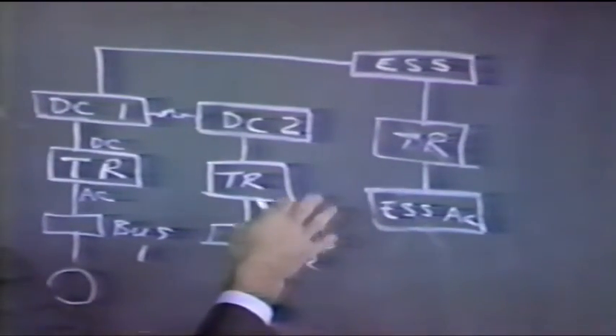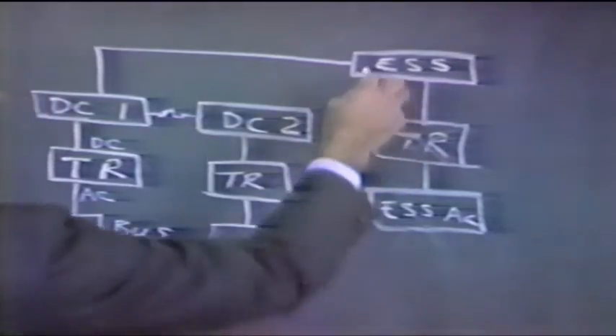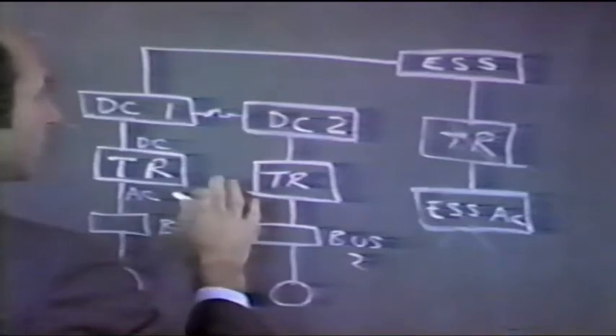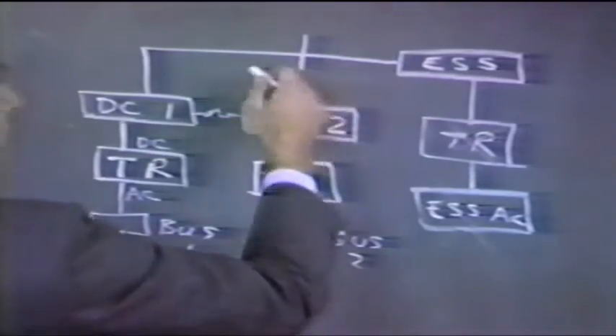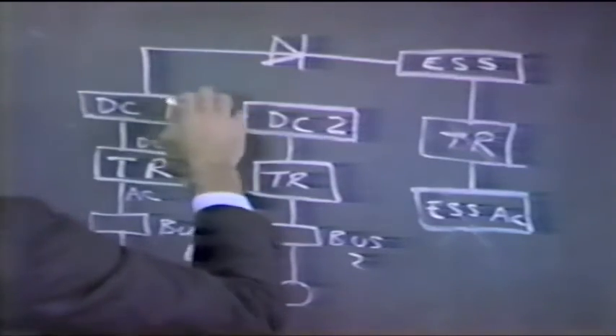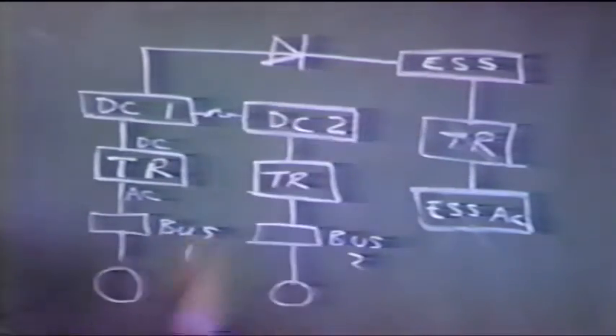And to make sure that we don't get a reciprocal arrangement, to make sure that we don't drain off really important essential DC to power, say, number 1 and 2 if both of these TRs failed, we have a one-way street here, a blocking rectifier, so that the power can come this way, but it can't go back the other way.